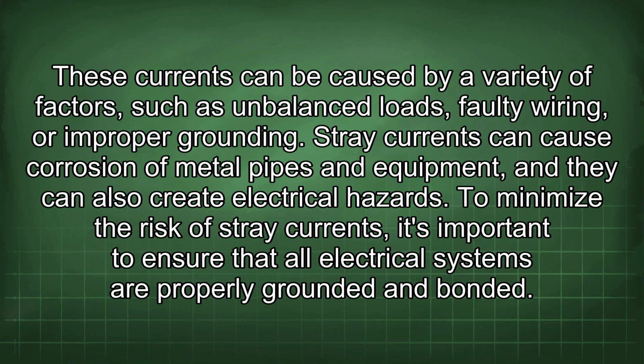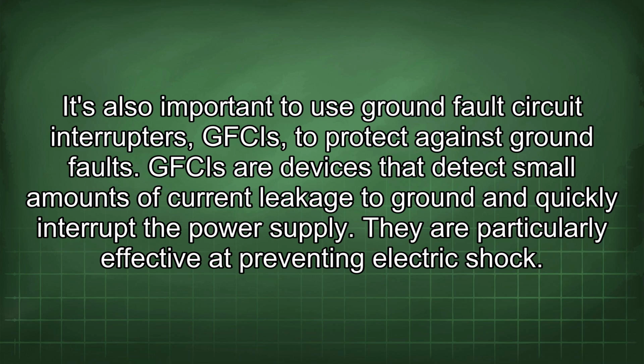These currents can be caused by a variety of factors, such as unbalanced loads, faulty wiring, or improper grounding. Stray currents can cause corrosion of metal pipes and equipment, and they can also create electrical hazards. To minimize the risk of stray currents, it's important to ensure that all electrical systems are properly grounded and bonded. It's also important to use ground fault circuit interrupters (GFCIs) to protect against ground faults. GFCIs are devices that detect small amounts of current leakage to ground and quickly interrupt the power supply. They are particularly effective at preventing electric shock.